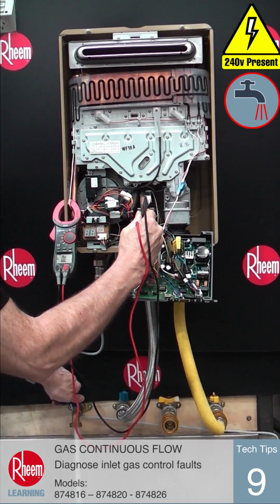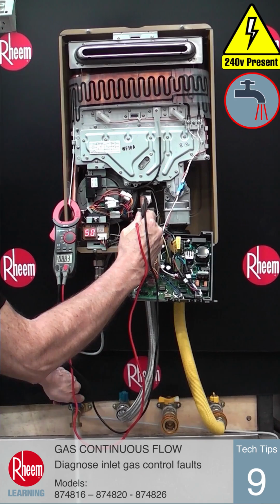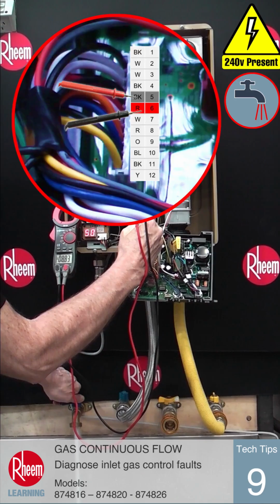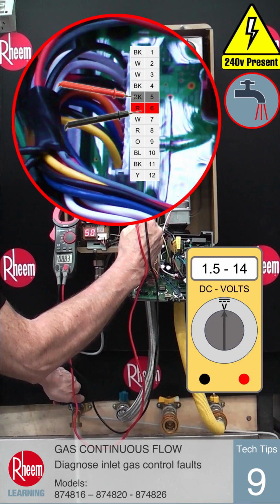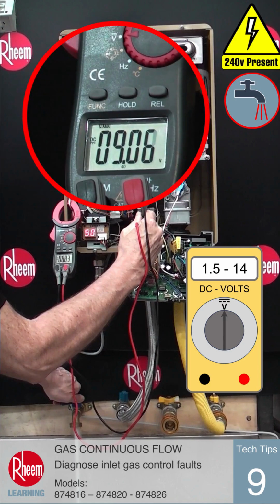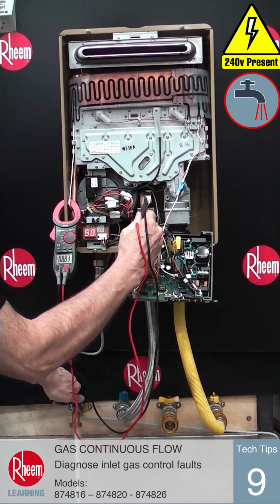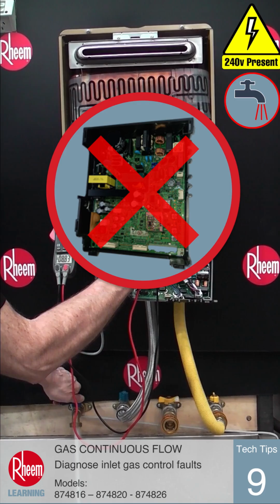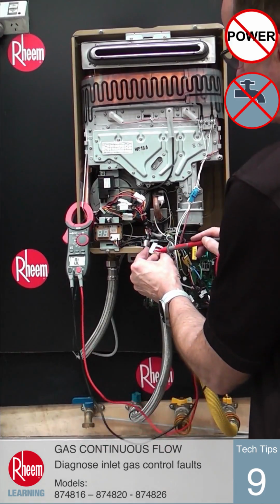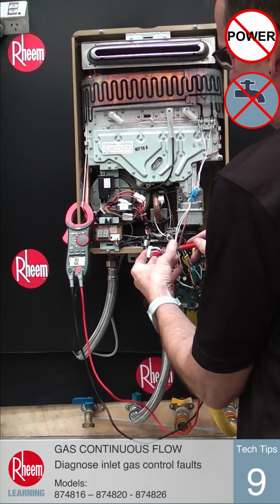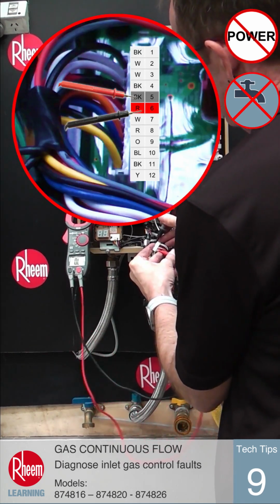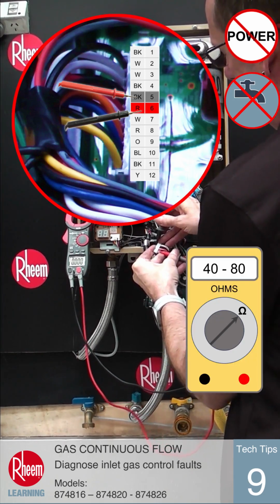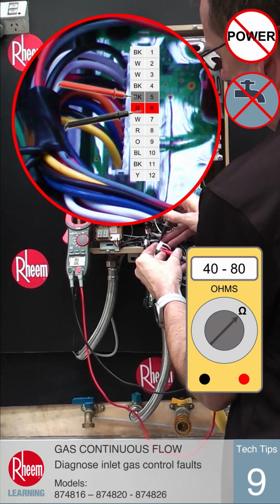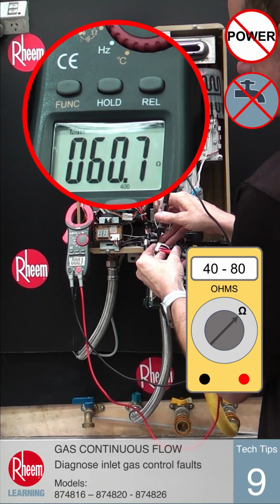With power on and water flowing again, use a test meter to measure voltage between pin 5 black and pin 6 red. The reading should be between 1.5 and 14 volts DC. If this is not correct, the PCB is faulty and should be replaced. If the voltage is correct, turn off power and unplug connector I from the PCB and measure the resistance between pin 5 black and pin 6 red. This reading should be between 40 and 80 ohms.